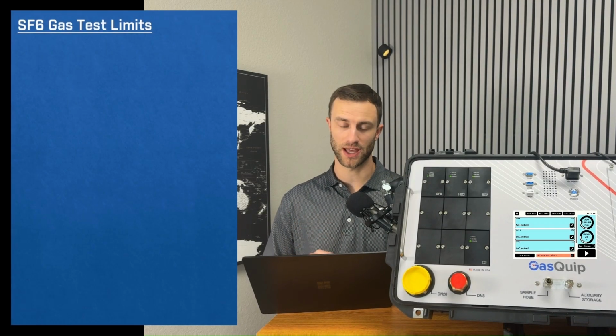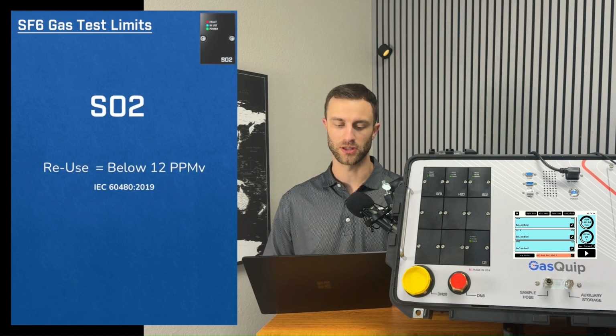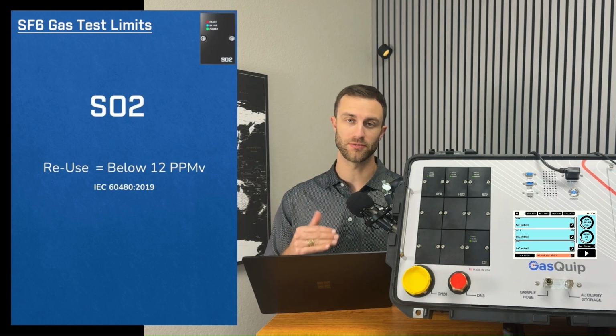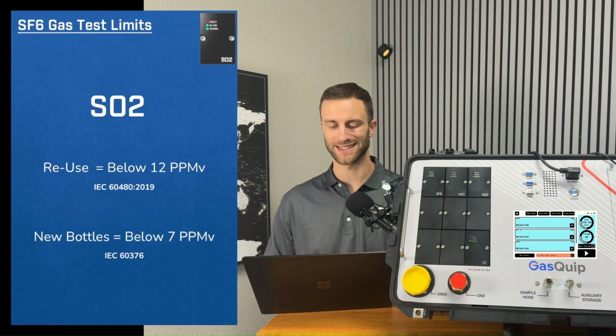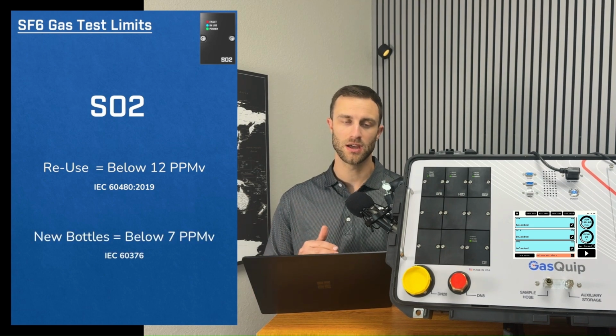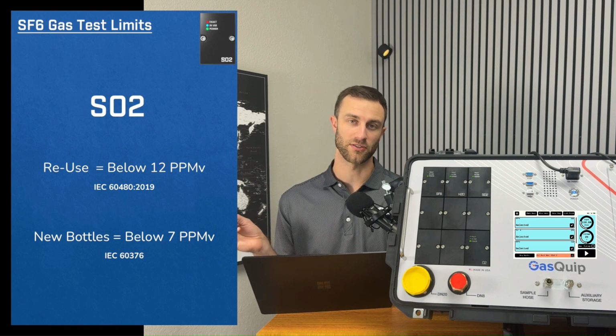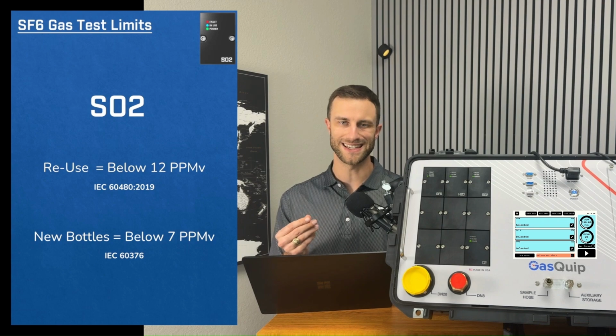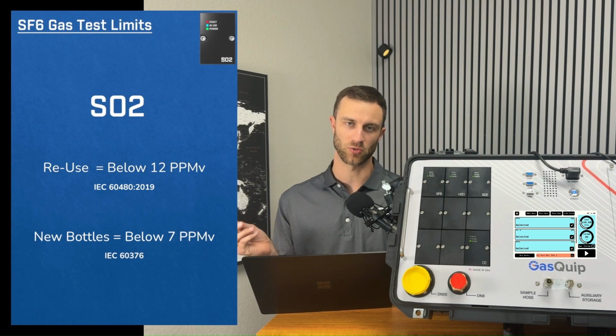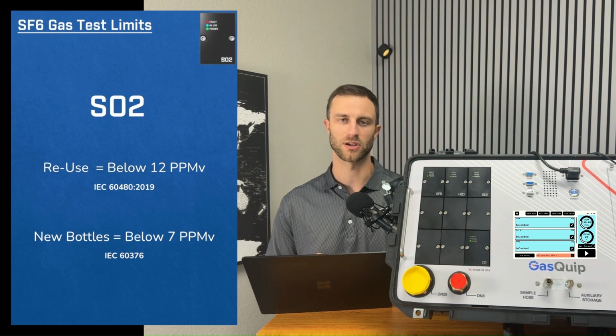The test limits for SO2 are also based on the reuse and new gas. So for the reuse, it needs to be below 12 ppmv, and for new bottles of gas, it needs to be below 7 ppmv. As a side note, if you do have gas that tests some level of SO2 in it, I would recommend flushing out your analyzer with nitrogen. It's a good way to flush out all of the sticky SO2 and the other acidic components that can build up in that gas. If you don't have nitrogen, you can run some tests of SF6 and then pump that into an empty cylinder.